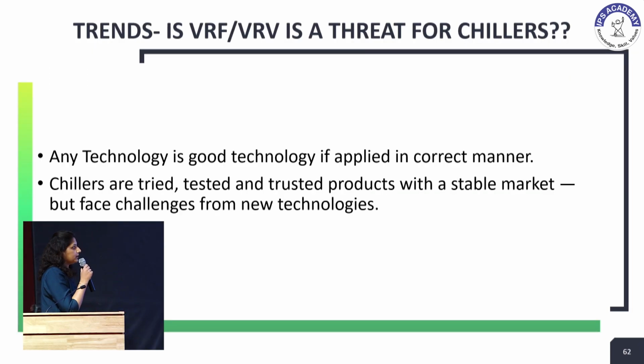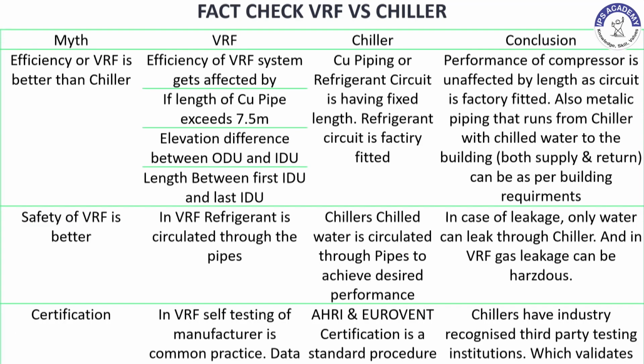Again, when we talk about chillers, there is another technology which is today available, which is a VRV or a VRF technology. So we will quickly go through and look how it is a threat for chillers. When we see what is the difference between a VRV and a chiller, in a chiller we are chilling water. However, in a VRV or a VRF, we are chilling the refrigerant. So we see that the refrigerant is flowing in the entire building. When you compare it with the chiller, the chilled water is flowing in the entire building. So when you talk about the safety hazards, if the refrigerant flowing inside the building leaks, it is hazardous to the health.